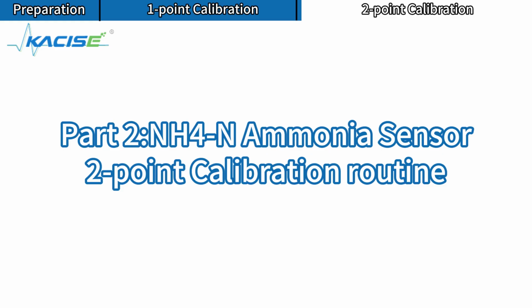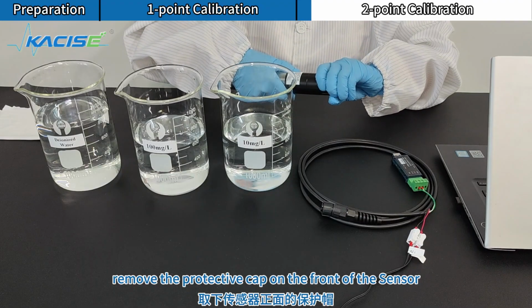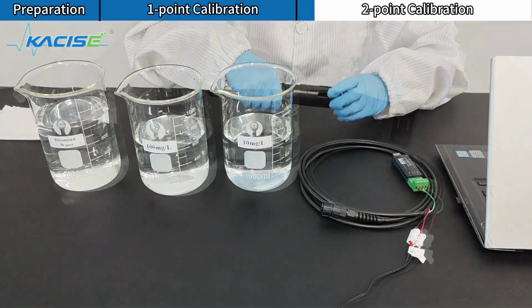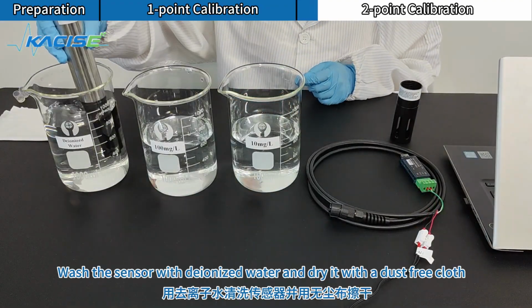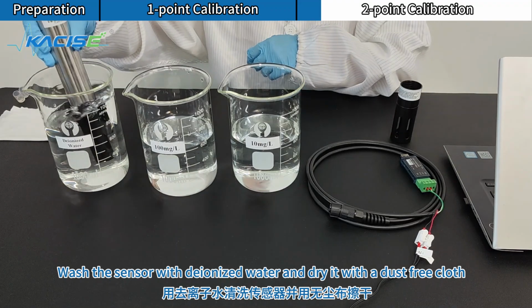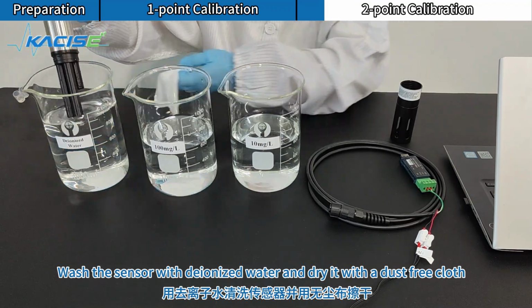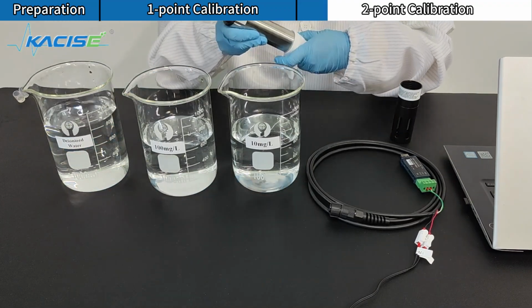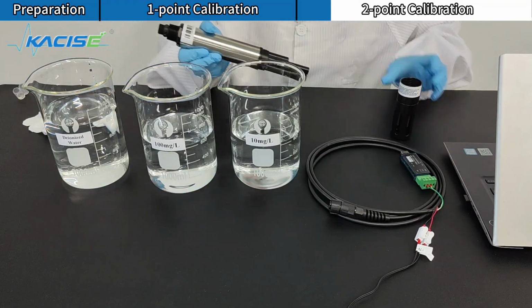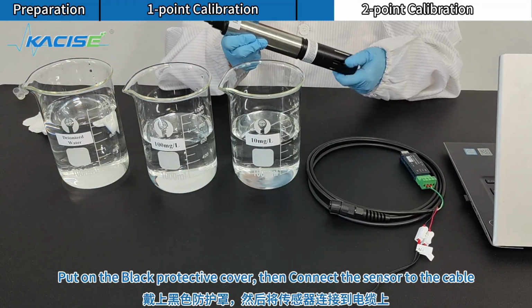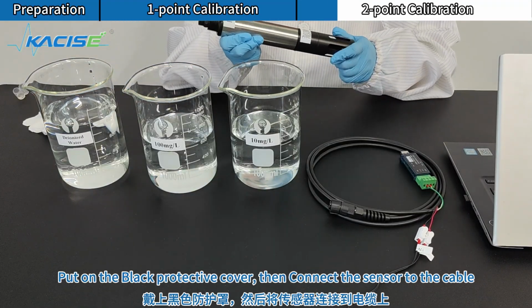Part 2, NH₄-N Ammonia sensor. 2-point calibration routine. Remove the protective cap on the front of the sensor. Wash the sensor with deionized water and dry it with a dust-free cloth. Put on the black protective cover, then connect the sensor to the cable.